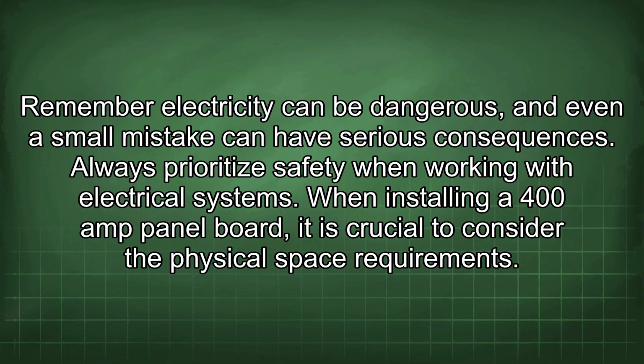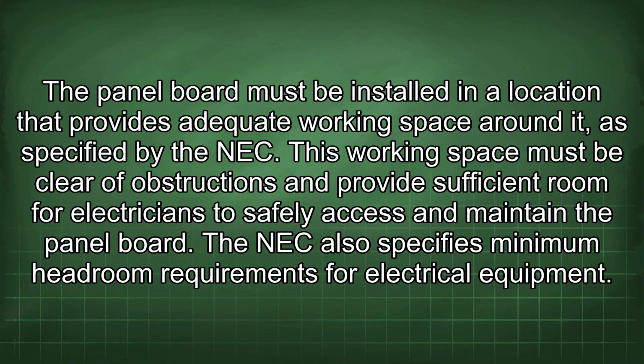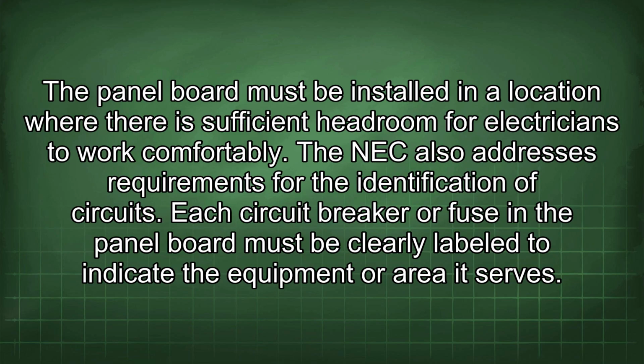When installing a 400 amp panel board, it is crucial to consider the physical space requirements. The panel board must be installed in a location that provides adequate working space around it, as specified by the NEC. This working space must be clear of obstructions and provide sufficient room for electricians to safely access and maintain the panel board. The NEC also specifies minimum headroom requirements for electrical equipment. The panel board must be installed in a location where there is sufficient headroom for electricians to work comfortably.